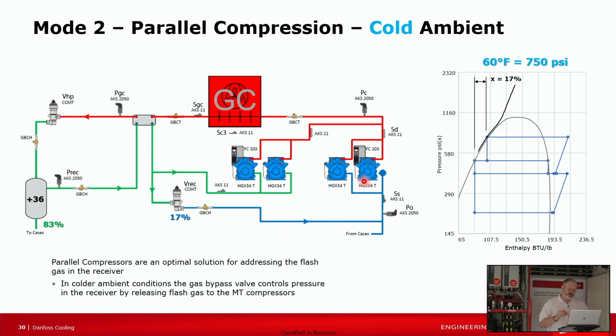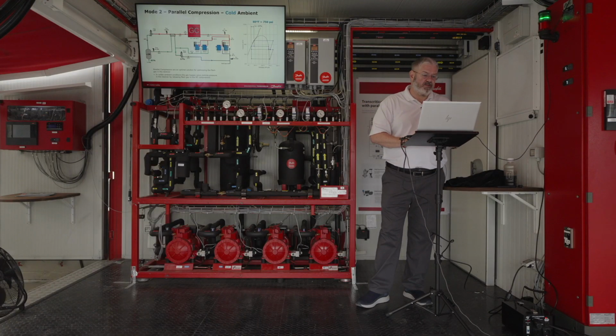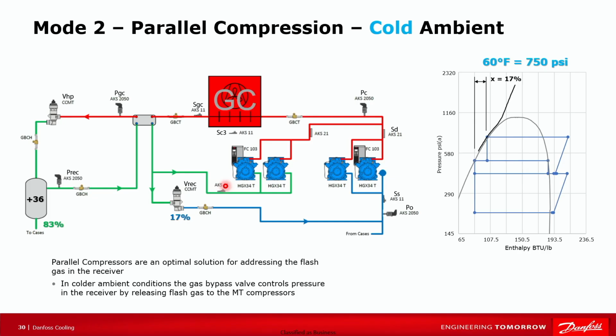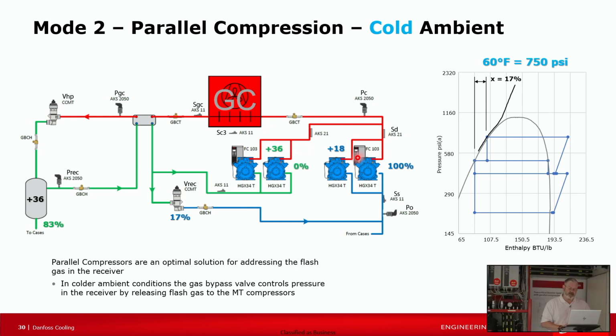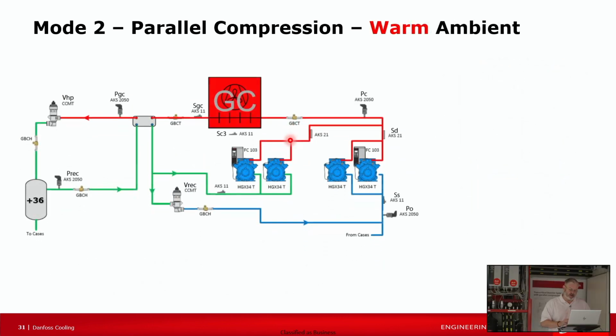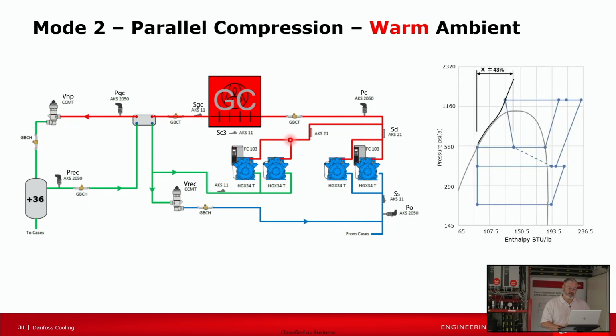And also, it's not enough flash gas to keep one of the parallel compressors actually running. It would chatter and bang on and off, even with a VFD limiting the frequency to 30 hertz. So in cold ambient, you bought your parallel compressors for nothing because they're not used. However, you still have 100% of your load going to the medium temp, nothing going to parallel. However, in a warm ambient, they are brilliant.